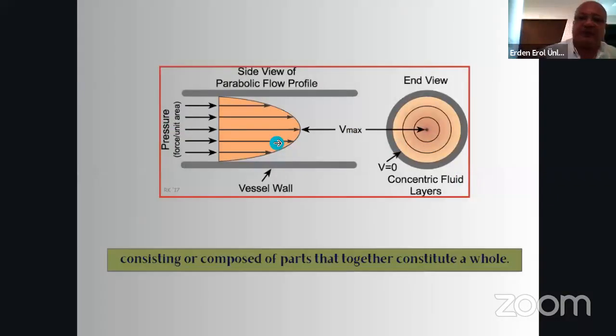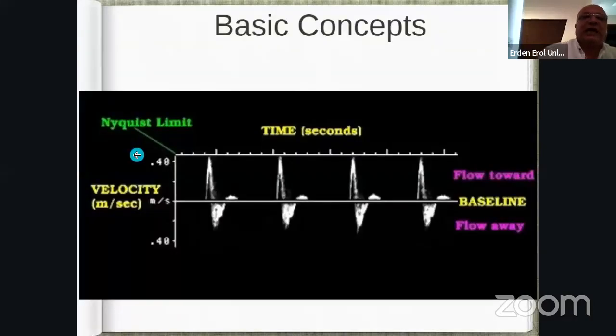So based on this knowledge, people produced two kinds of Doppler in the ultrasound machine. One of them is the continuous wave Doppler. The other is the pulsed wave Doppler. These are two different Doppler modes in the ultrasound machine. Continuous wave Doppler, how does it function? There are two crystals. One always transmits the sound, and the other part of the crystal receives the returning echoes from the targeted object. This is the continuous wave Doppler.